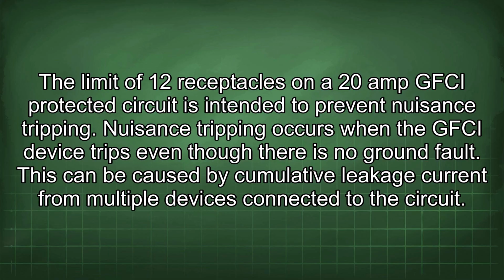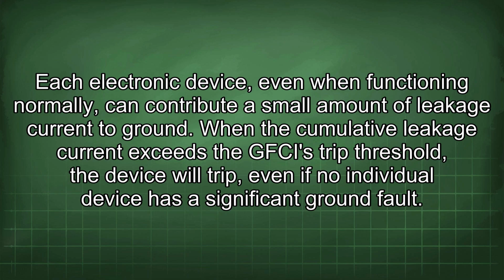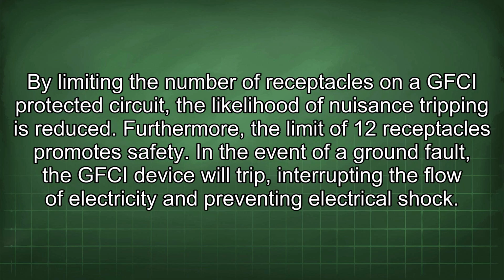This can be caused by cumulative leakage current from multiple devices connected to the circuit. Each electronic device, even when functioning normally, can contribute a small amount of leakage current to ground. When the cumulative leakage current exceeds the GFCI's trip threshold, the device will trip, even if no individual device has a significant ground fault. By limiting the number of receptacles on a GFCI protected circuit, the likelihood of nuisance tripping is reduced.